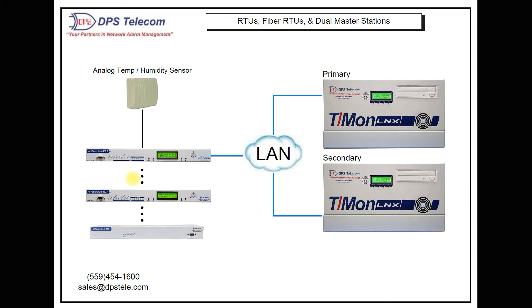You have 32 discrete inputs, so you can take in 32 contact closures. You have eight analog inputs, and one of those analog inputs would be used for a temp and humidity sensor — you'd use one input for temp and another for humidity, giving you temperature and humidity with a pretty high degree of accuracy. That's obviously very important at any remote infrastructure site that may have servers, radios, or any kind of equipment, where you've got to know the cooling system is working.